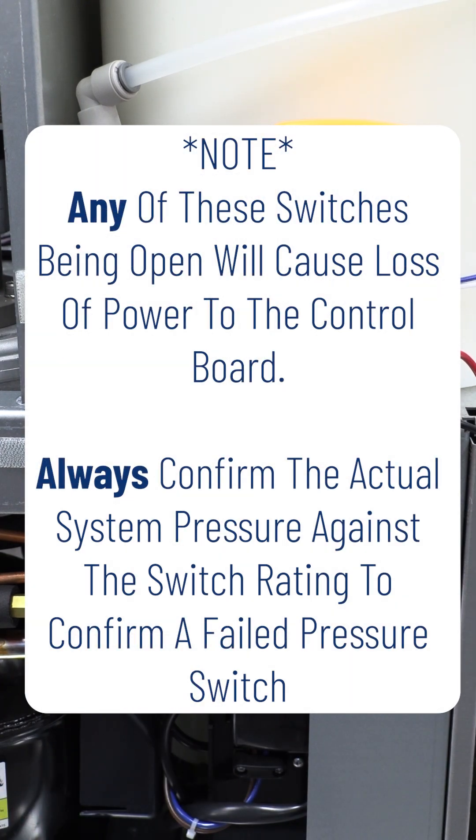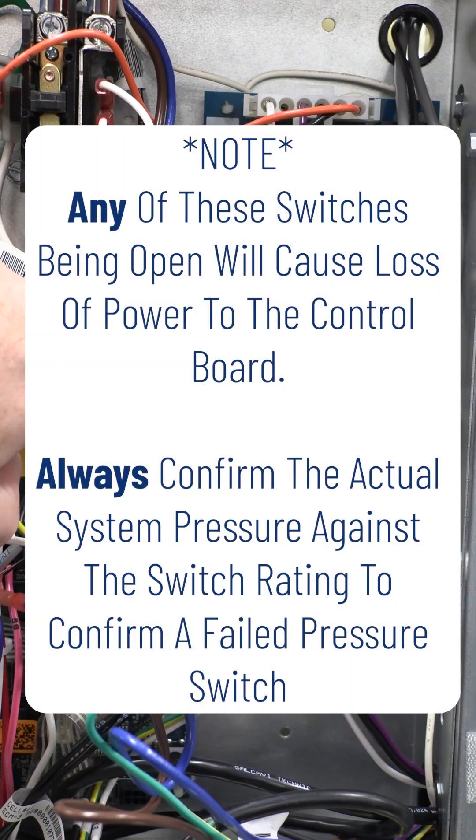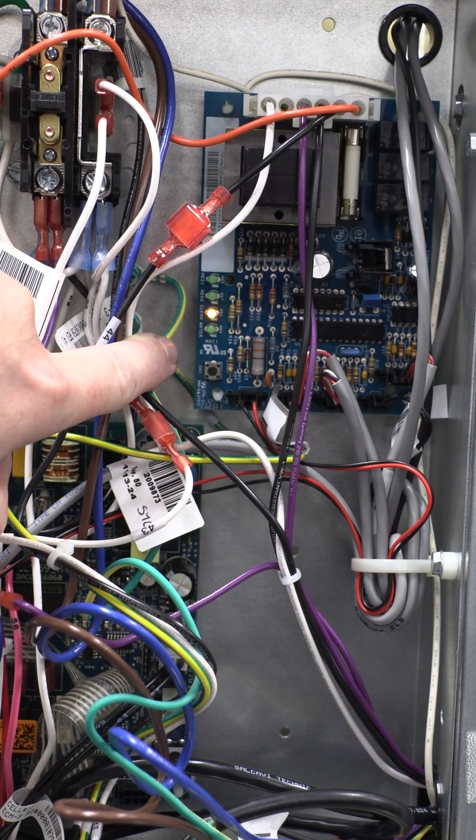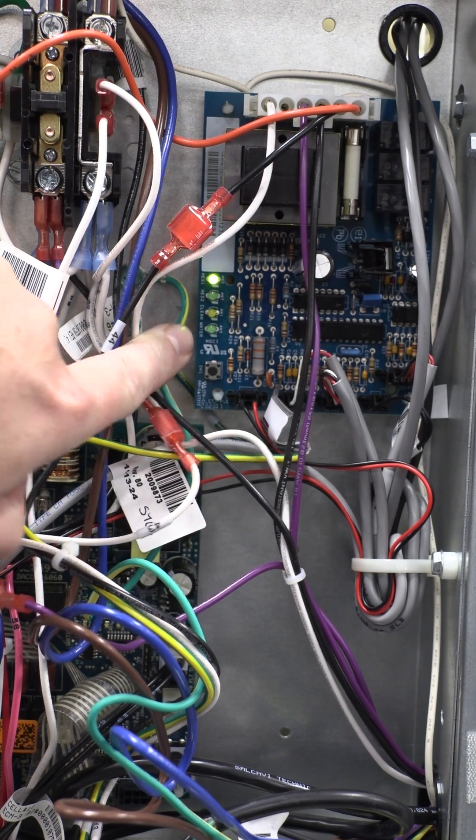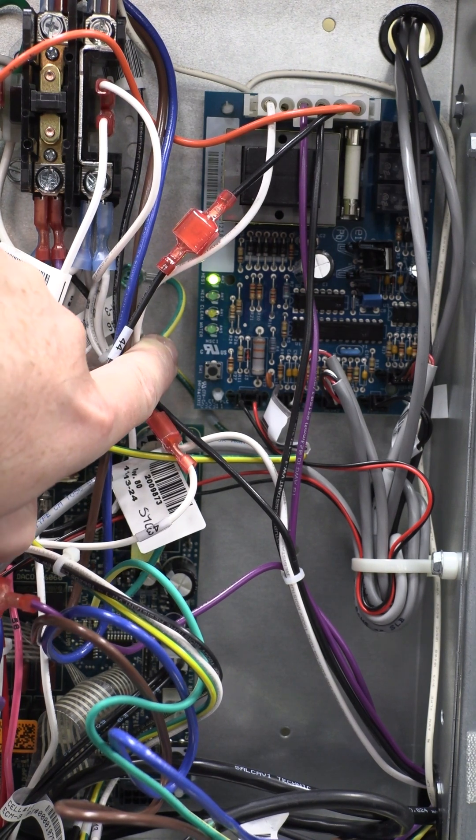I just got done replacing that high pressure cutout switch that failed on this machine. As you can see, I've restored power to the machine. Our board now has power as it should and we are in a delay. As you just heard, the delay ended. Contactor pulled in, our compressor is running, and we'll be making some ice. Close to the next one.